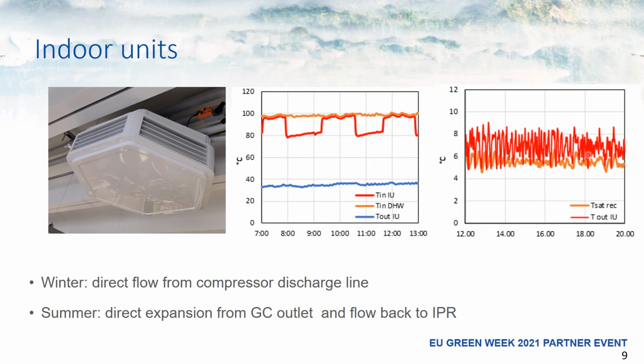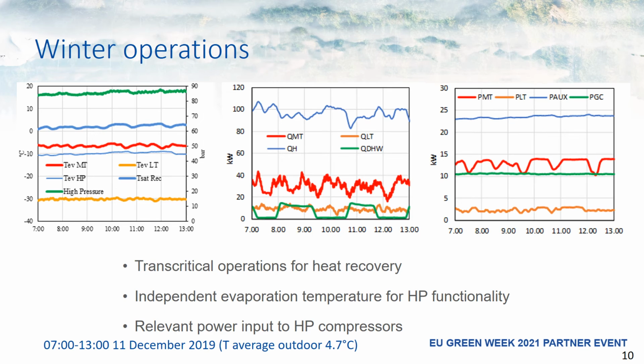In the summertime, the CO2 flows inside the coils at the saturation temperature of the receiver, which is about 5 degrees, and it flows back to the intermediate pressure receiver. Here are some examples of winter operations. So in the winter time, you can see that the pressure is always transcritical. This is because heat recovery is always operating.